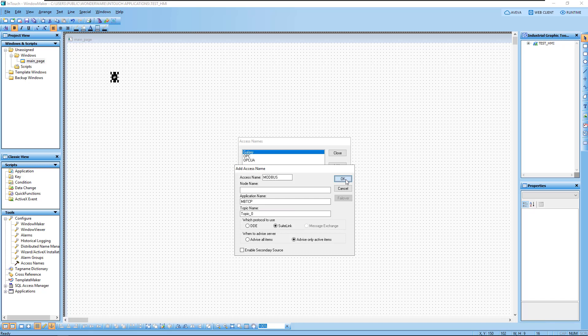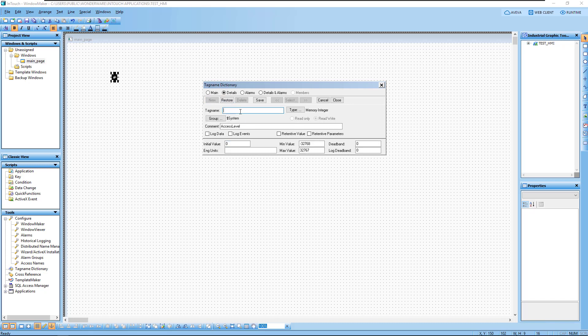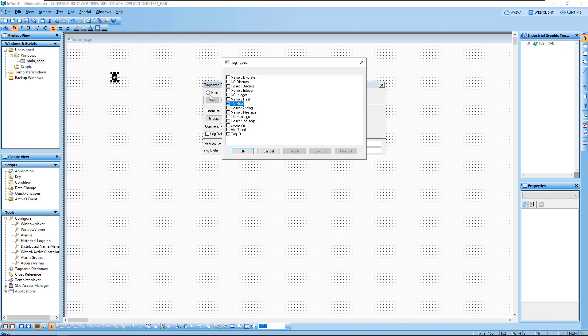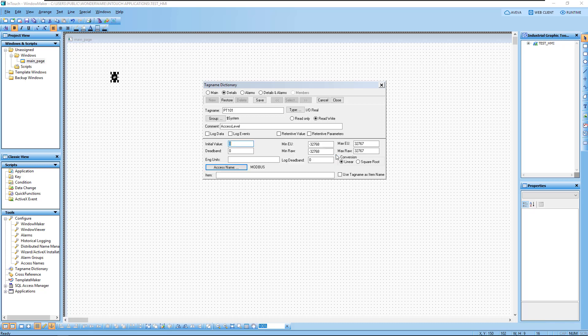Close that. Now we're going to add some tags under this access name. We need to create a new tag. We already added the item name in the SMC, so this is 'PT101'. The type is IO Real, and the access name is 'modbus'. Close. Since I already defined this inside the SMC item referencing register 40001, I just use the tag name as the item name.